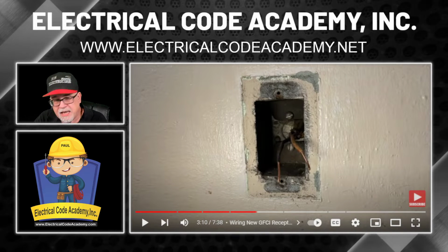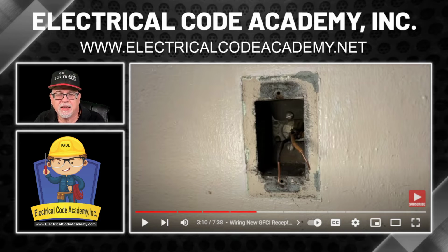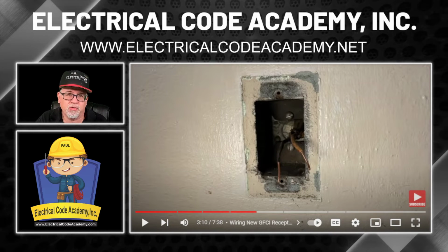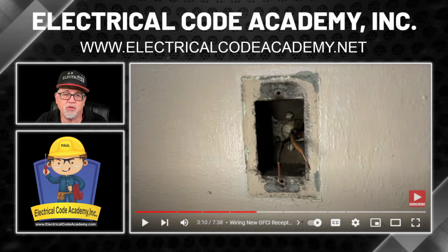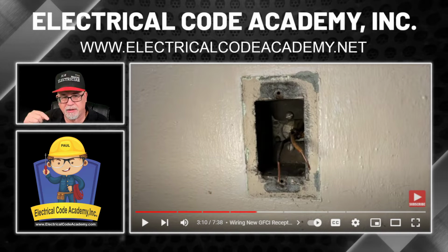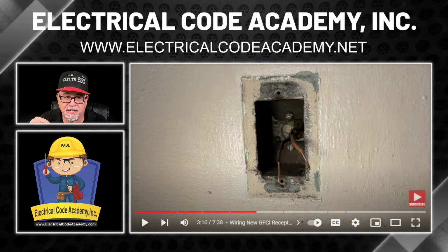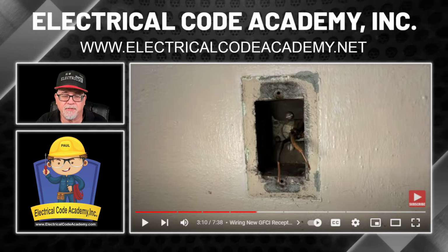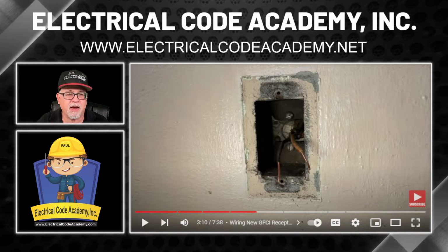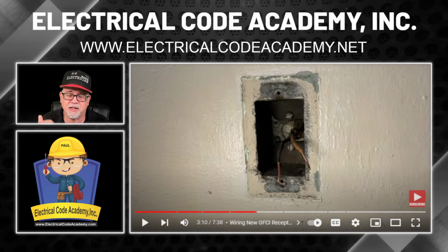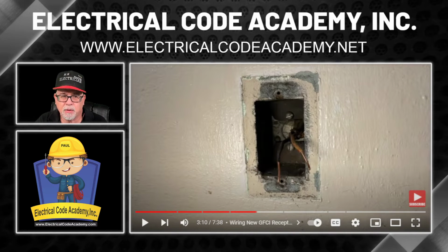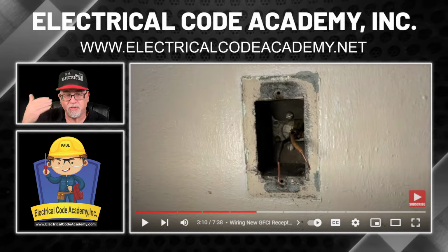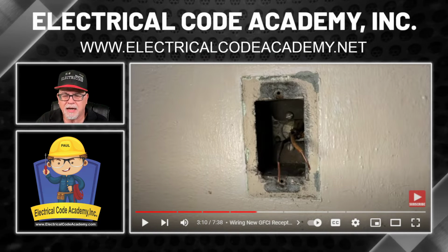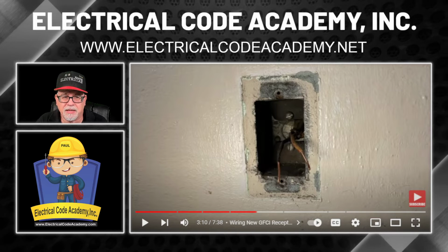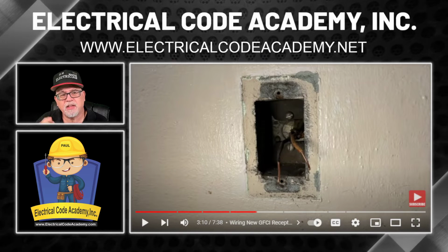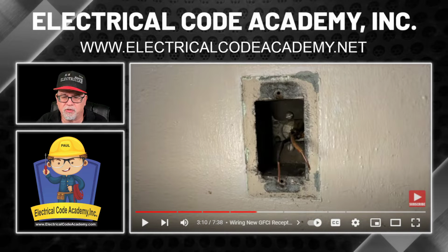Now, MC cable, metal clad cable, doesn't use the armor on traditional MC as an equipment ground. You have an equipment ground inside the cable, right? Either green insulated or bare. It doesn't matter. UL 1569 doesn't care. Most manufacturers with this smaller branch style MC will put an insulated green equipment ground. As it starts getting larger into feeder size MC, it tends to become bare. But the code allows for it. Not a problem either way. But the big issue is the armor on MC cable is not to be used as an equipment ground.